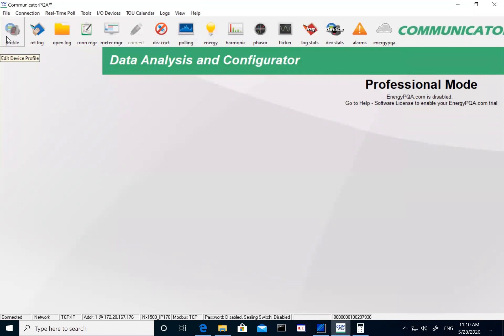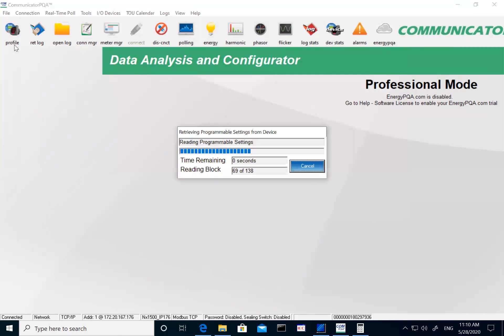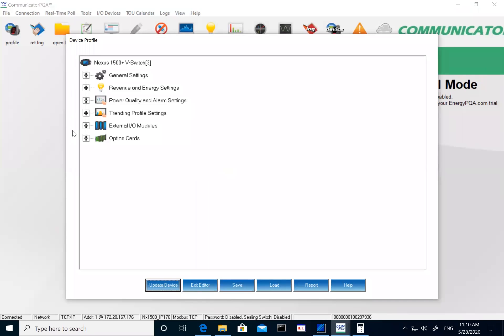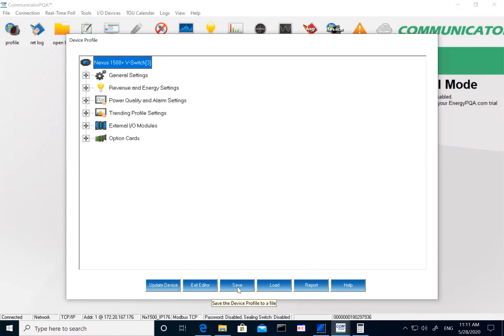Any changes you want to make on the meter are done through the profile, so I'll go into the profile. This is the typical profile — it has a tree menu on the top, shows the type of meters, and on the bottom shows different options. You can update the device to load settings back into the meter, exit, or save this profile offline. Customers who buy 10 to 15 meters can save the profile and load it into all those meters, including all DNP settings, logging, power quality, CT/PT ratios, and IP address settings.